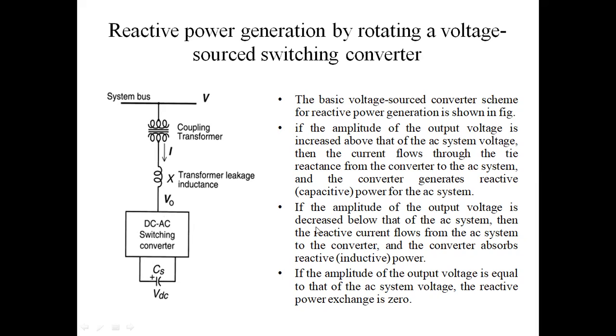If the amplitude of the output voltage V0 decreases below the system AC bus voltage V, then the reactive power current flows from the AC system to the converter — the converter absorbs reactive power. When V0 < V (i.e., V > V0), the converter is absorbing reactive power. Third condition: if the amplitude of the output voltage V0 equals the AC system voltage V, the reactive power exchange is zero.